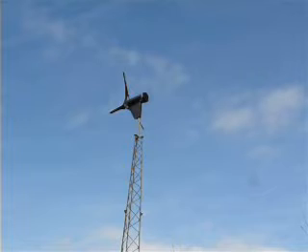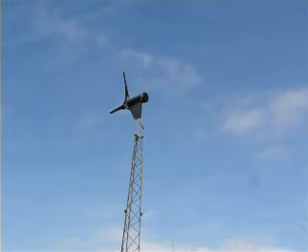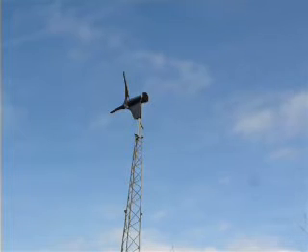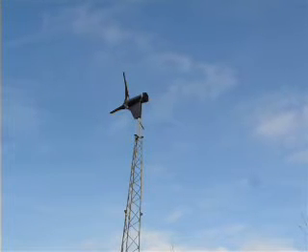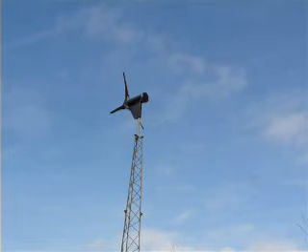On an upwind machine, the tail that directs the turbine blades into the wind is designed to fold and therefore reduce overspeed in high winds. Overspeed is a particular problem of turbines, whereas you want the power, but there comes a point where mechanical damage could occur.